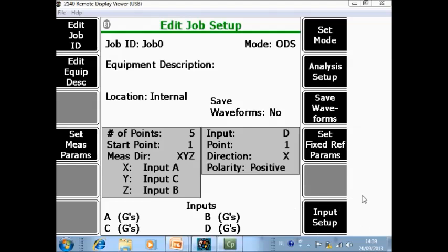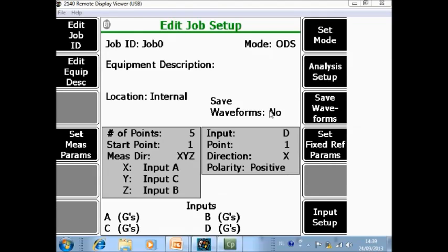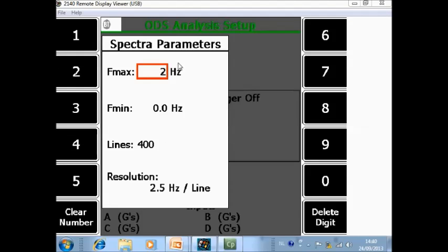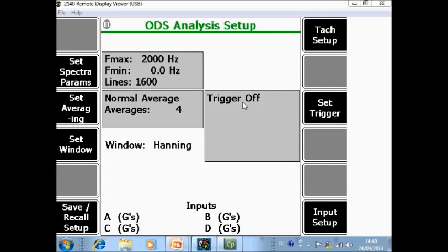Here you can configure the sensors — I will work with 4 accelerometers. I will also save the waveforms. The last thing to do is specify how I want to measure, so go to F8 analysis setup. Here I specify that I want to measure up to 2000 Hz, with 1600 lines of resolution.